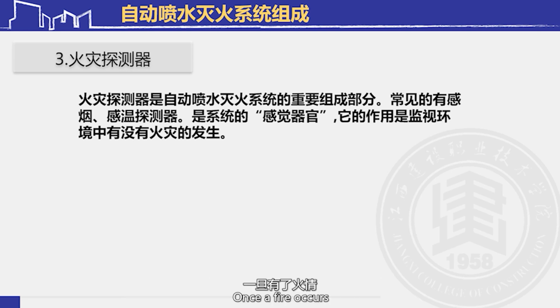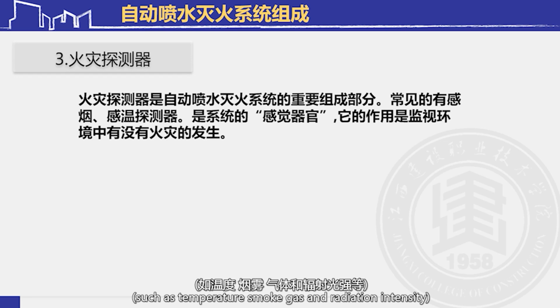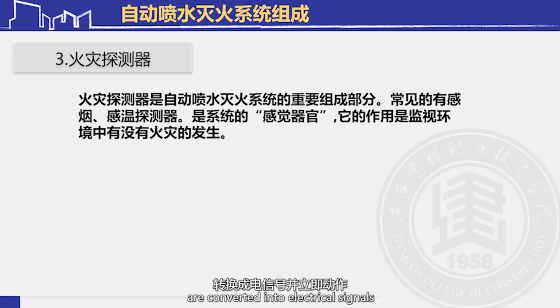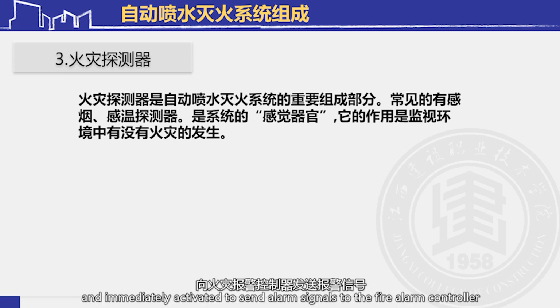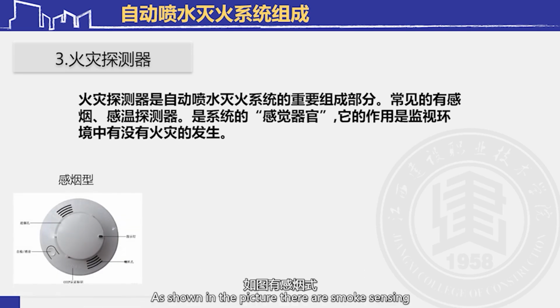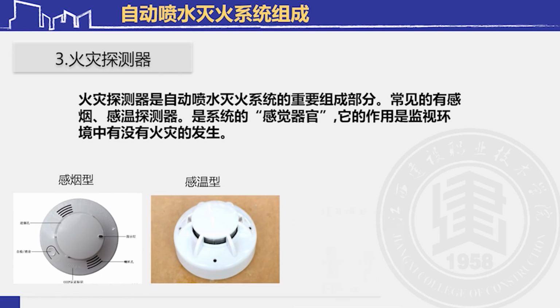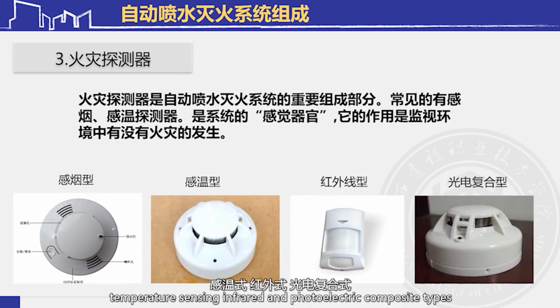Once a fire occurs, the characteristic physical quantities of the fire, such as temperature, smoke, gas, and radiation intensity, are converted into electrical signals and immediately activated to send alarm signals to the fire alarm controller. As shown in the picture, there are smoke sensing, temperature sensing, infrared, and photoelectric composite types.